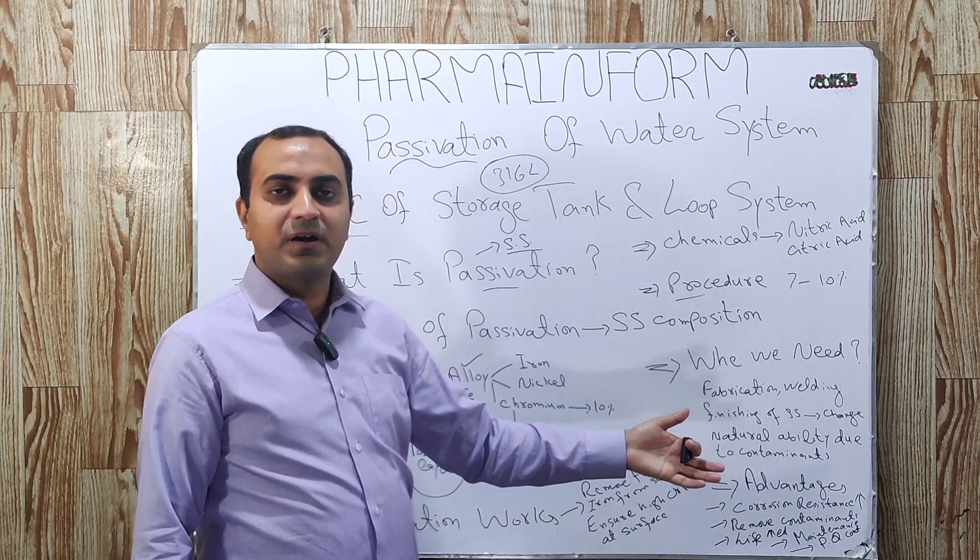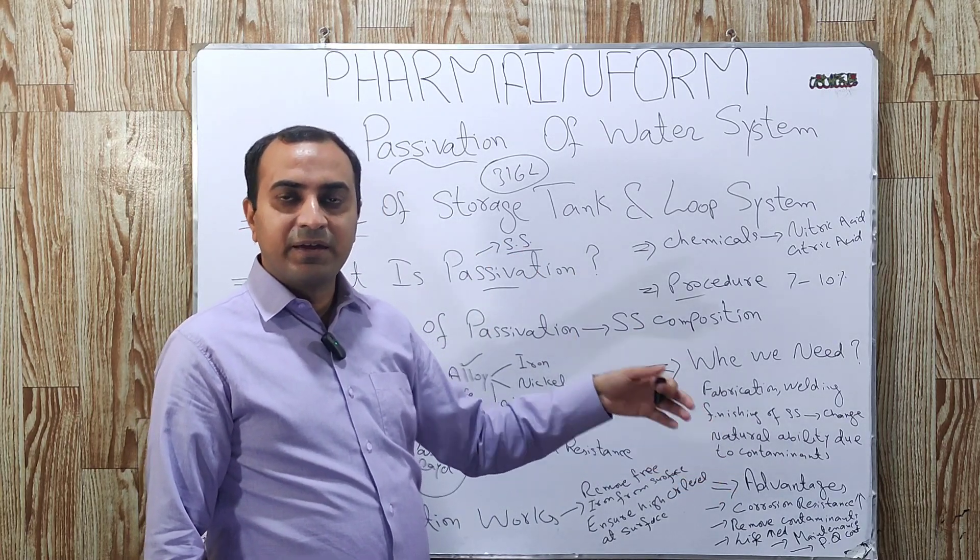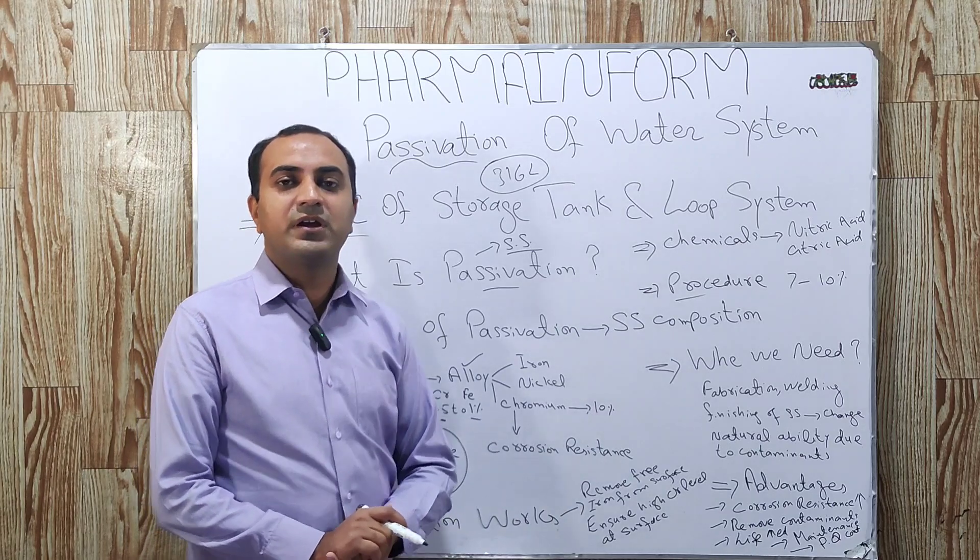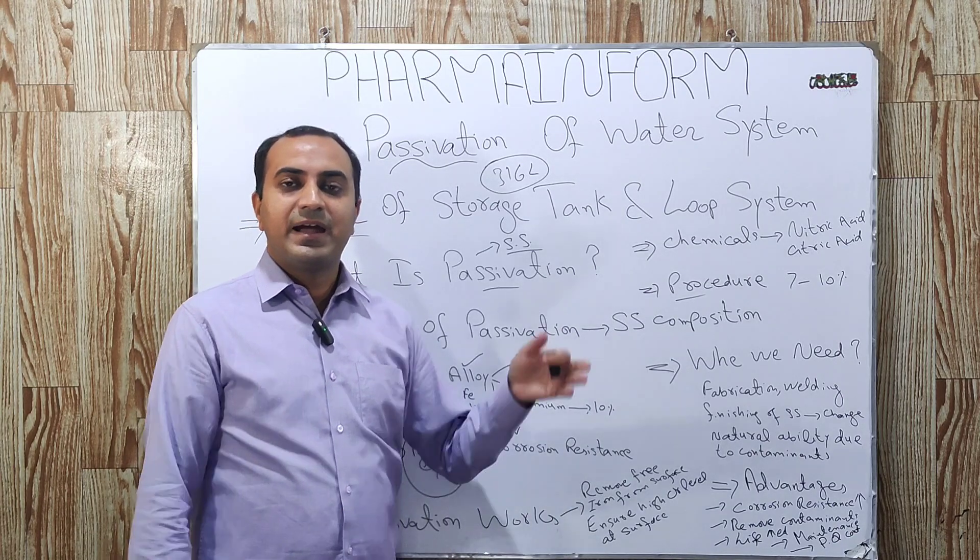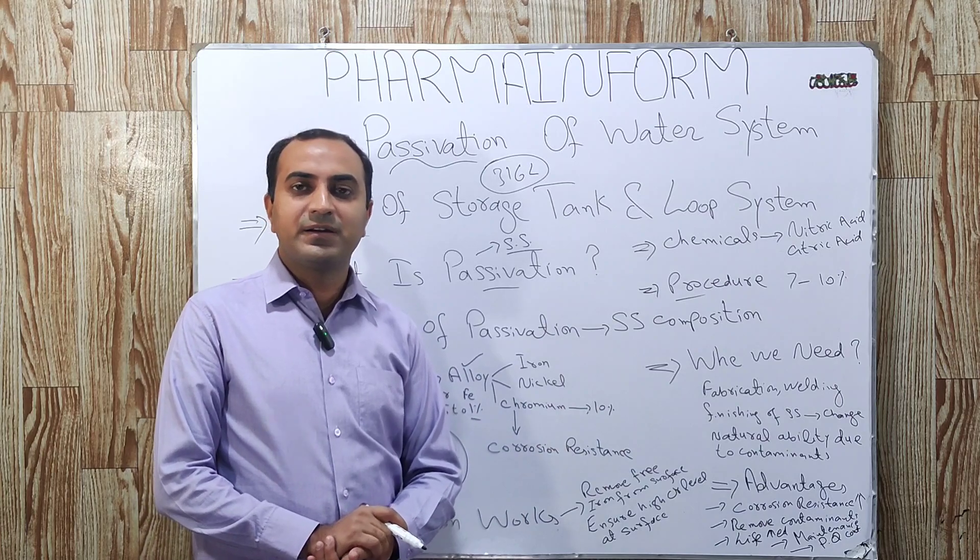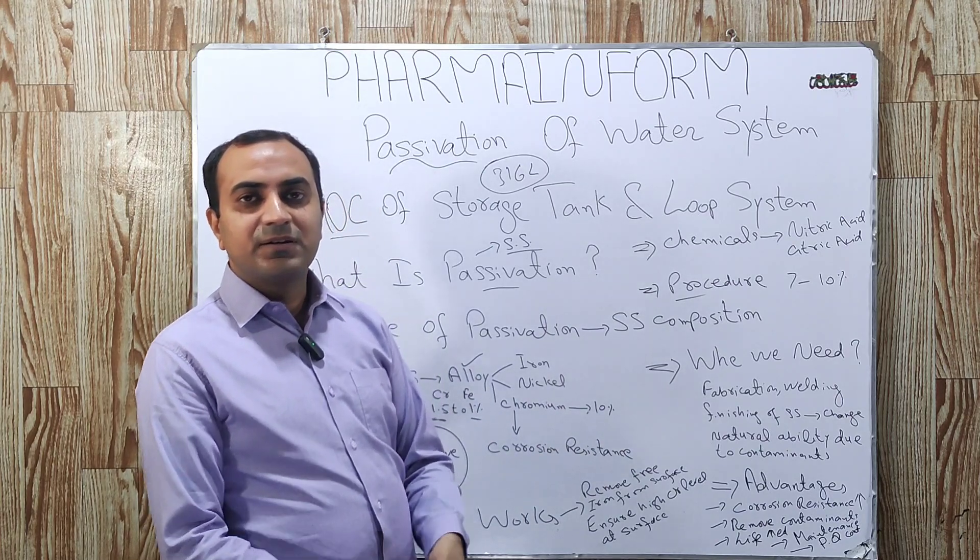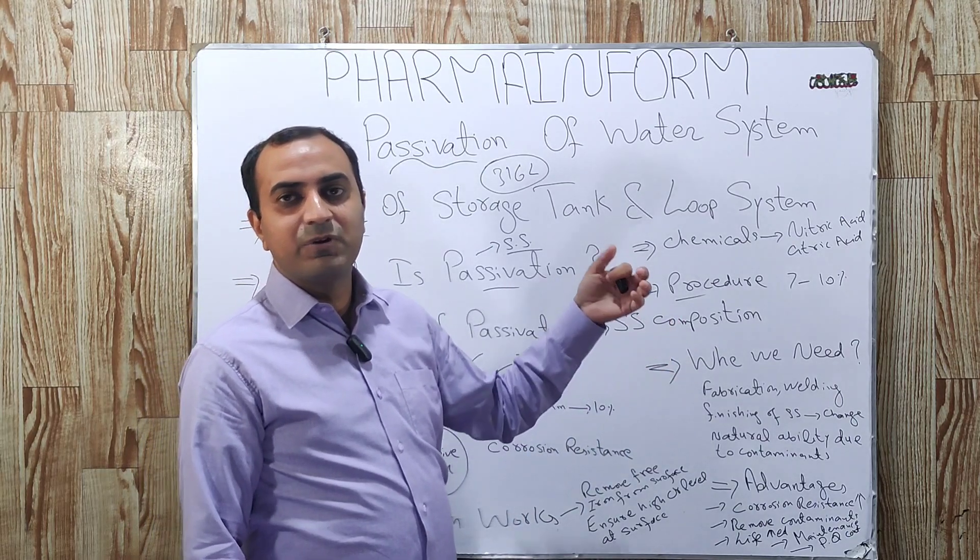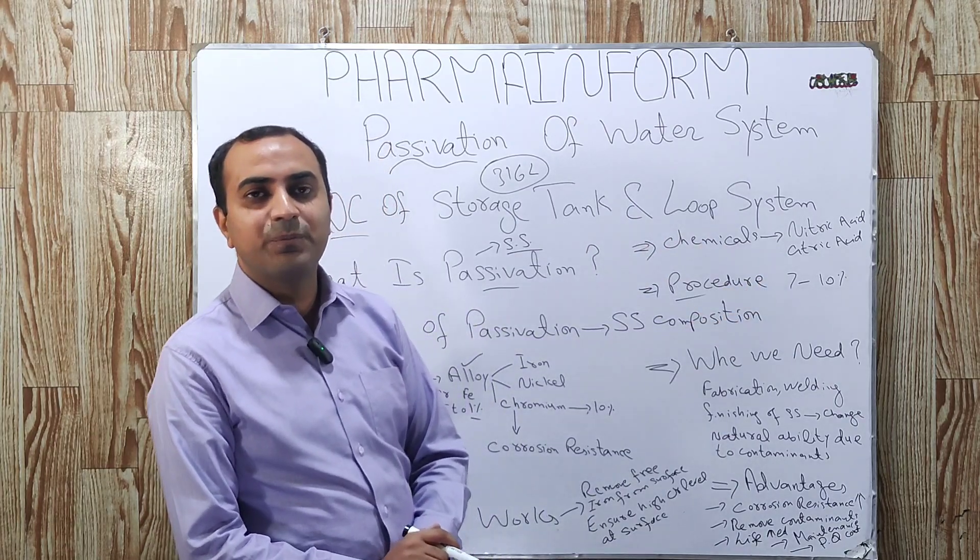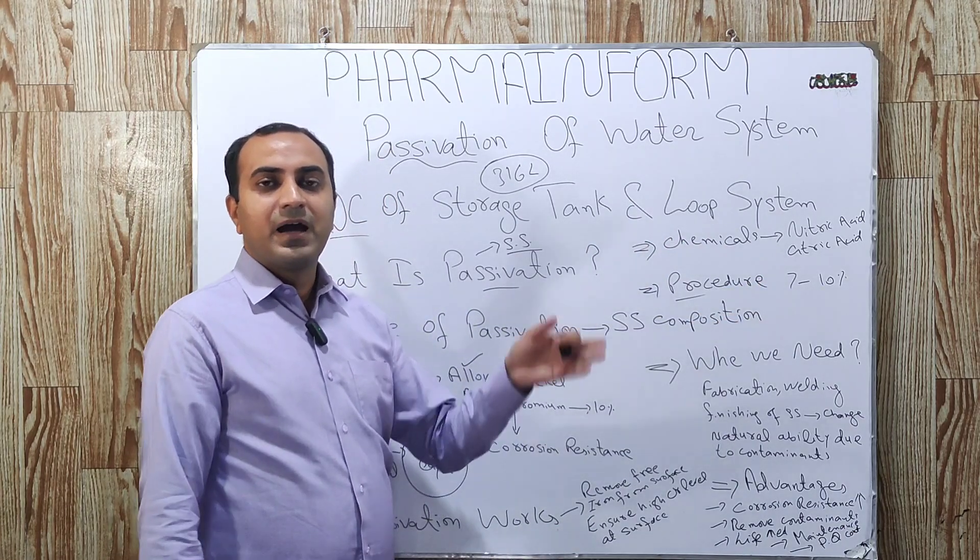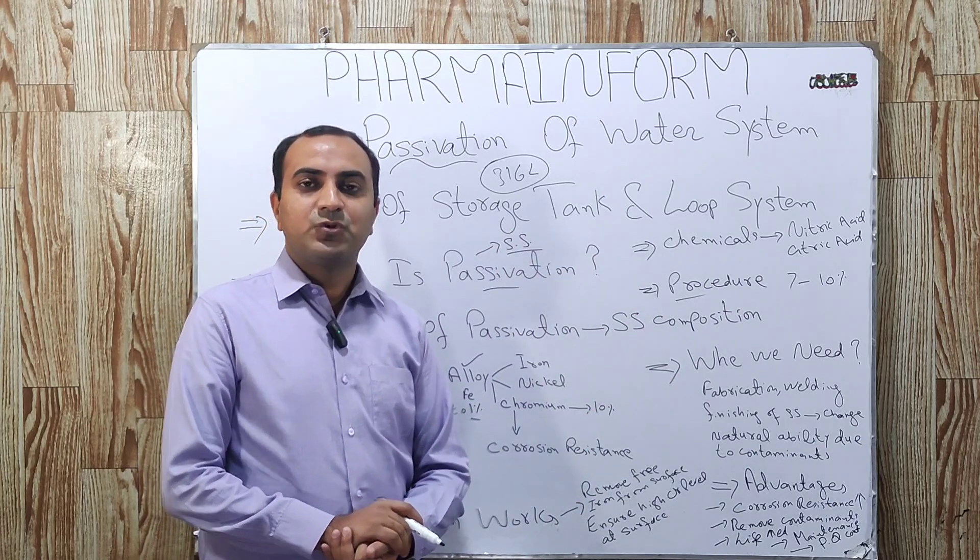After 1 hour, we discard this water and again fill it with water and circulate it again for 30 to 60 minutes and again check its pH and conductivity. The pH and conductivity of this water must be equal to the feed water and if the pH is according to the ranges, our passivation process is completed.